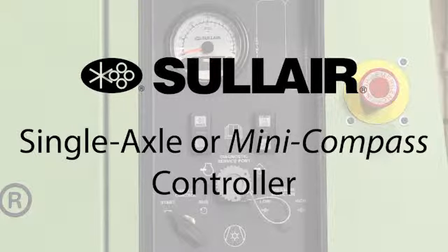The Sullair single axle controller, also known as the mini compass. The Sullair single axle or mini compass controller was designed for controlling the compressor system operation and access to adjustment of the machine parameters. It utilizes digital technology for performing maintenance operations that ensures accurate and safe operation of the complete compressor system. When a fault condition occurs, the controller will automatically shut down the machine to prevent injury to the operator or damage to the equipment.